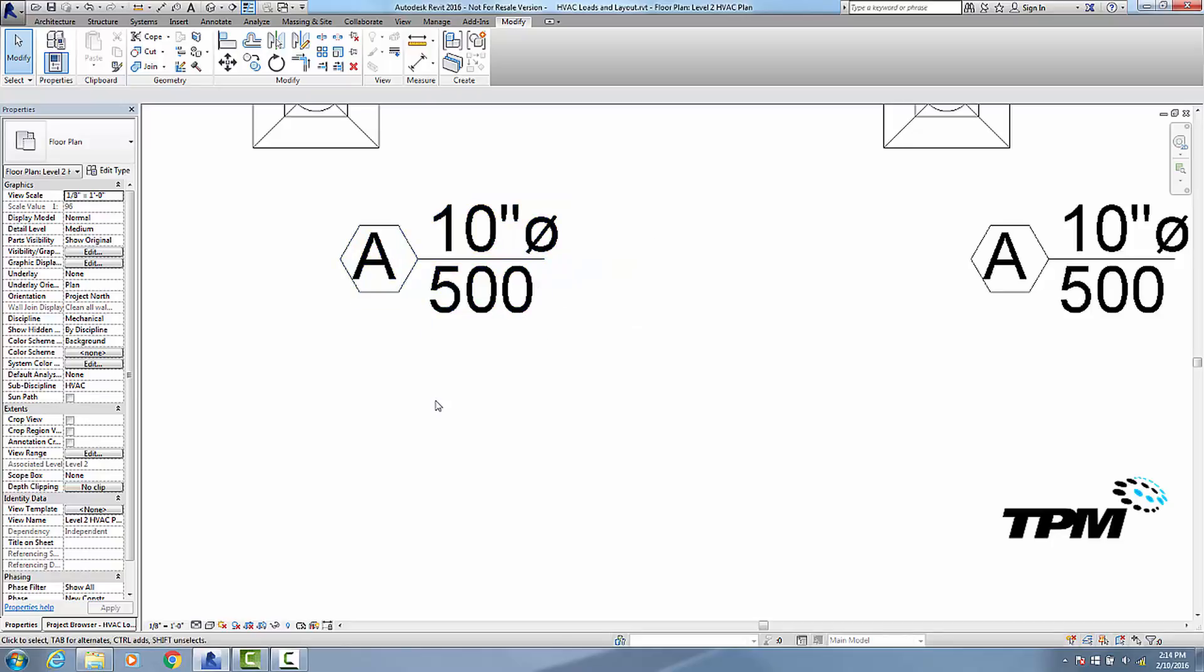Now if I wanted to get rid of the diameter symbol, I can get rid of the diameter symbol, but it has ramifications. It's not just part of the tag; it would get rid of diameter symbols all over. So if I had a duct that was a 10 inch round duct, it would simply say 10 inches. And I know a lot of people actually prefer it that way.